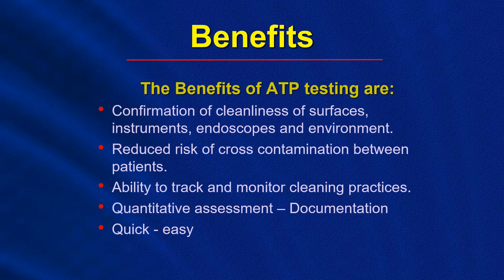Now, understand that anything that you're testing, especially surgical instruments, scopes, things like that, if you have above normal levels of ATP, all that means is that that device or those devices were not cleaned efficiently. They would have to be re-cleaned and retested to get an acceptable level of ATP before you can send them out for subsequent sterilization or high-level disinfection. But again, in 15 seconds, you'll get a readout of the ATP on whatever you're testing.